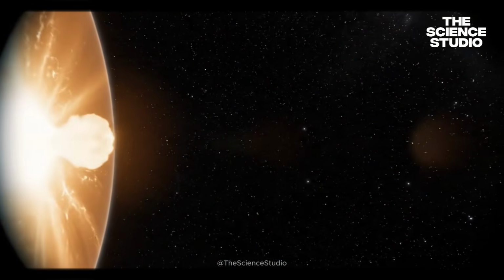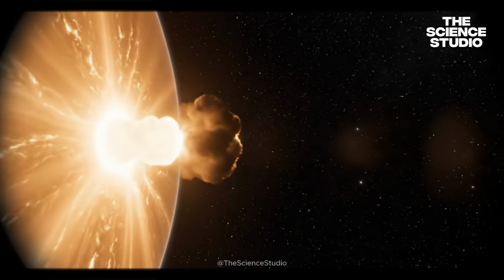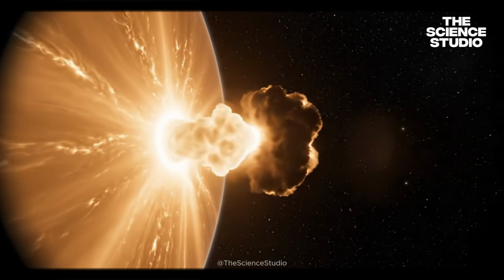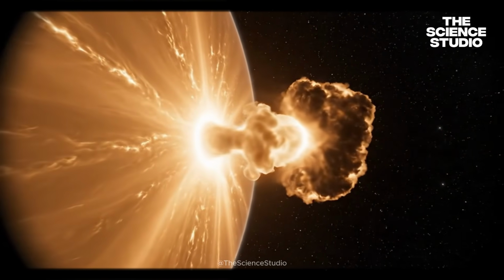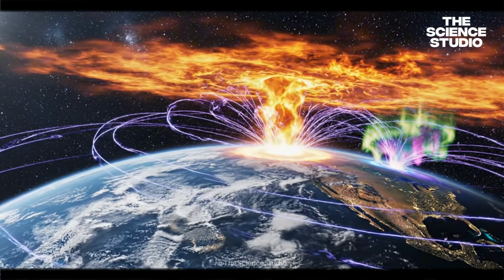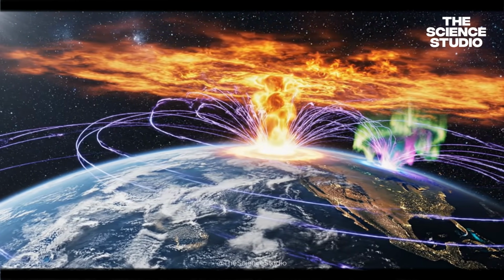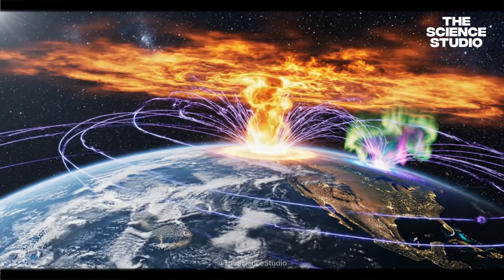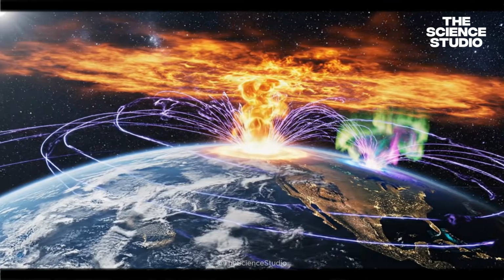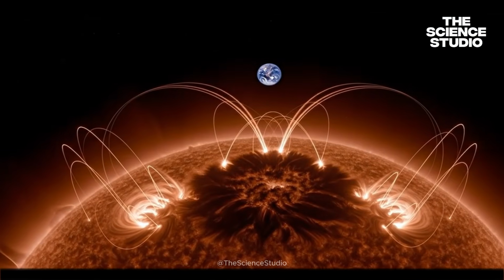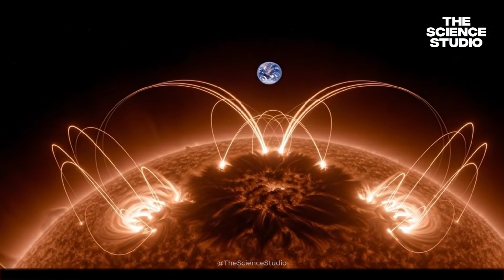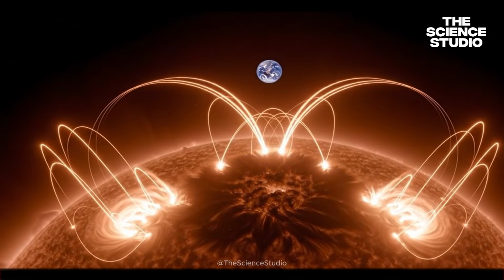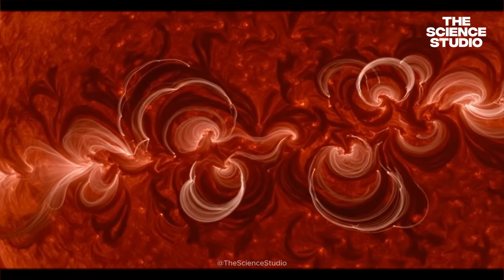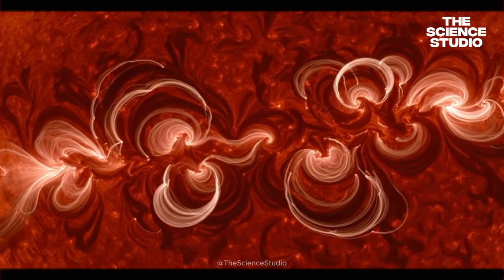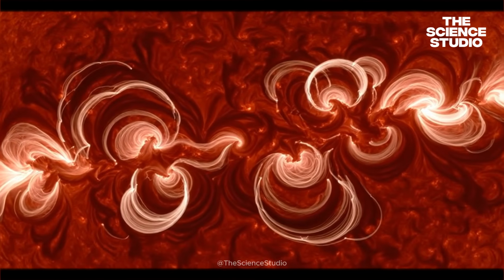That event lasted less than a day. This event lasted 4. The public understood this storm as a weekend storm, something that hit, produced Aurora, and passed. The storm ran 4 days. 4 consecutive days of geomagnetic disturbance means every GPS satellite in orbit corrected its trajectory 4 times. Every northern latitude transformer absorbed GIC current across 4 separate night cycles. 4 cycles of the same stress is not 4 times one event.